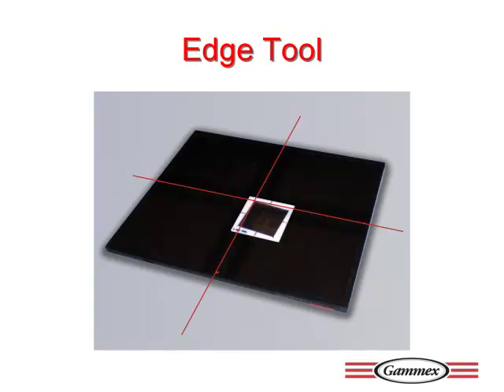The images are loaded into a file where they can be analyzed at any time. The edge tool software now allows users to easily generate MTF, DQE, and NPS data and to analyze it. Setup of the software is quick and easy as shown below.